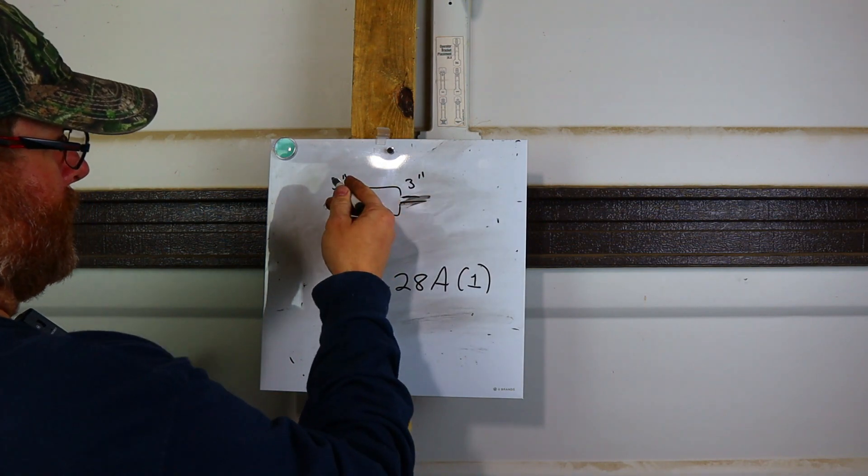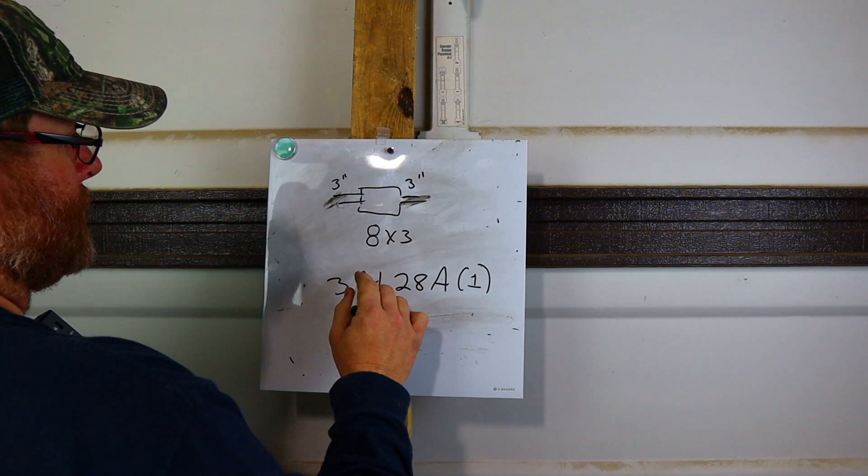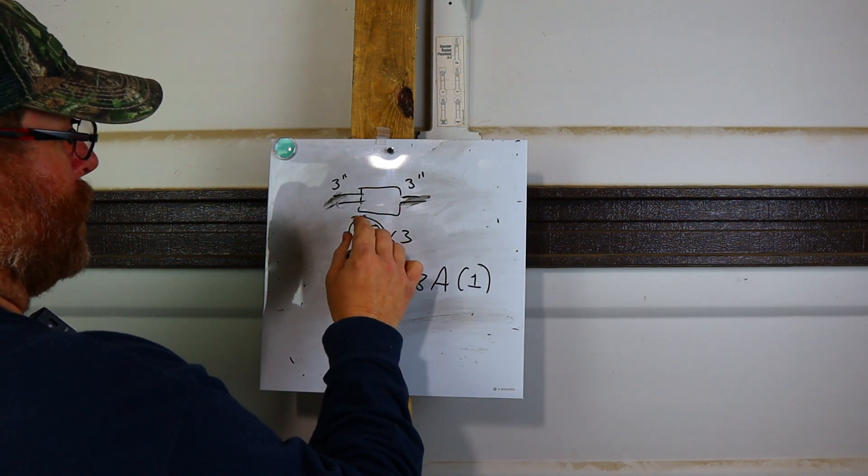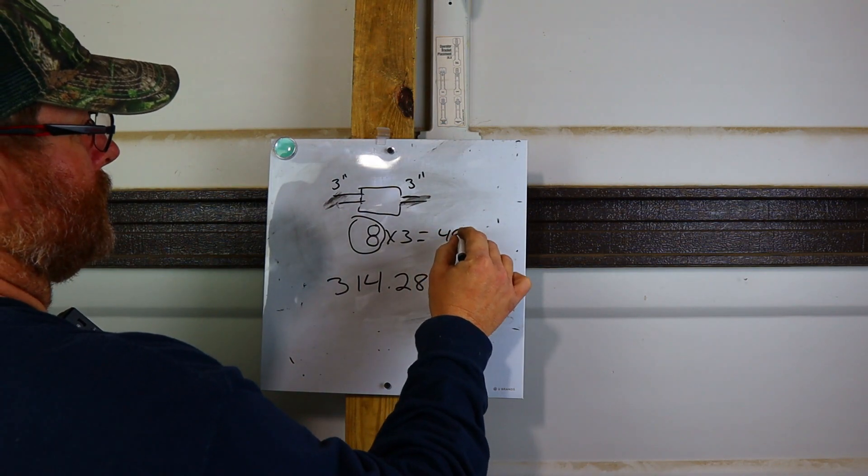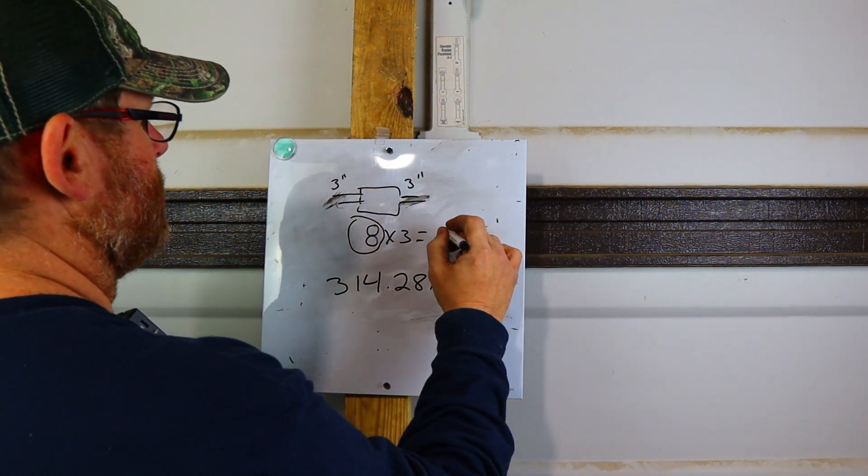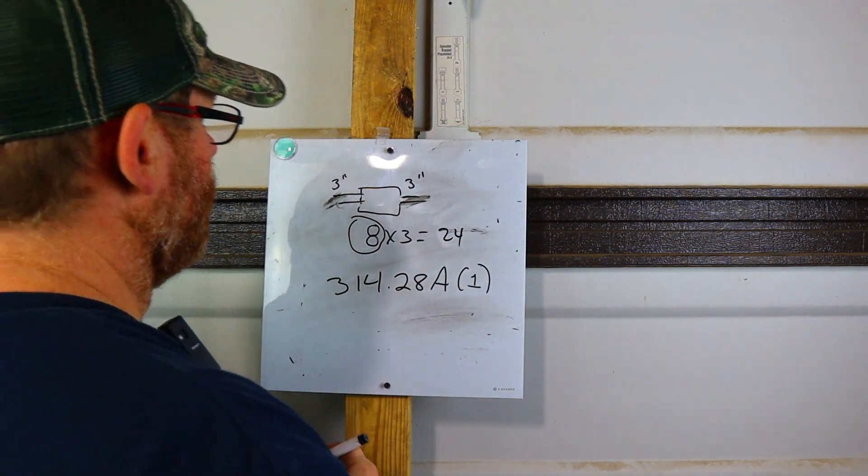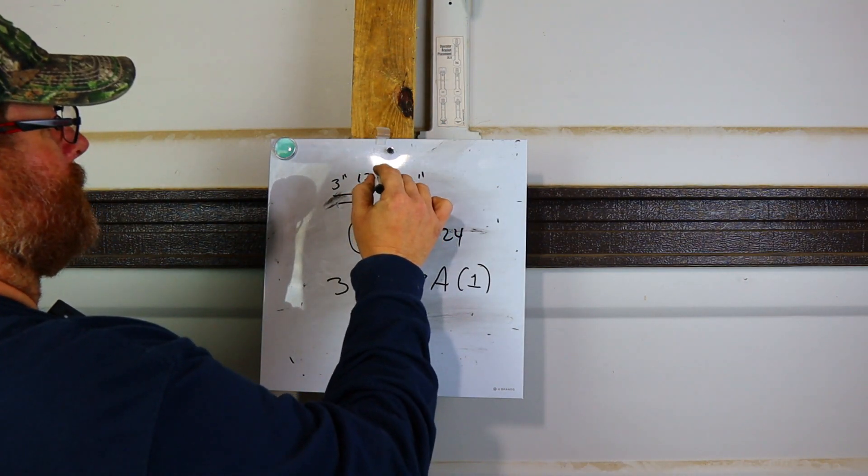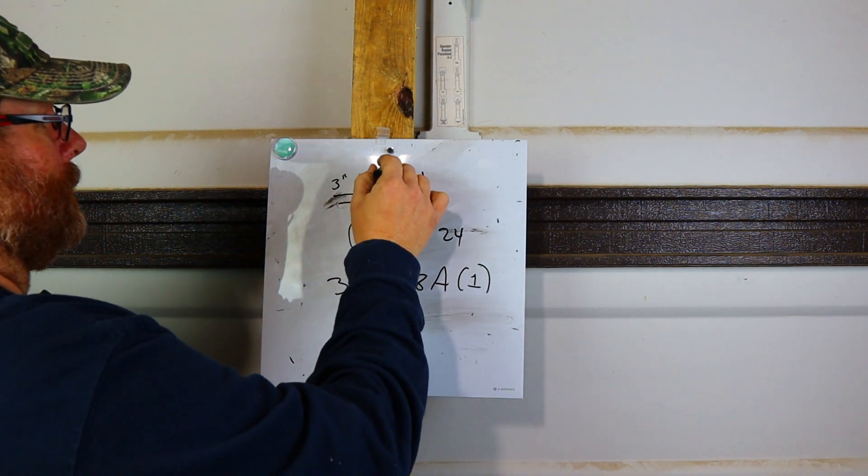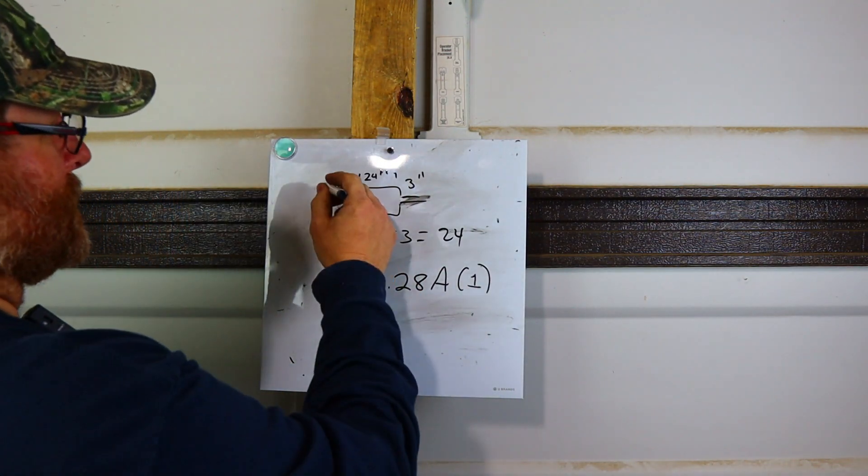So what you'll do is, because it's only a straight pull, you're just going to take one of these. It'll be 8 times 3 because 8 is the multiplier. 8 times 3 is 24. So you'll need from here to here a 24 inch box. Now that's what I said earlier, right? But I was talking about 2 inch. I'm just showing you.